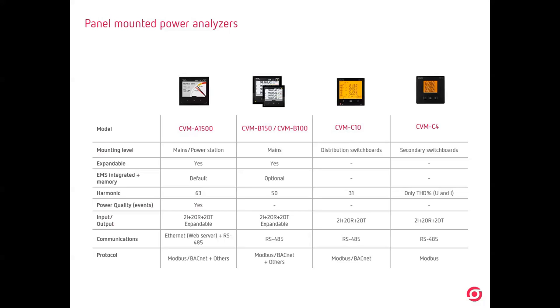Now we are reading harmonics, for checking the quality of consumption. CVM B is expandable. You can expand with more modules, and we are reading up to 50 harmonics. And CVM A is designed to be installed in mains, in the power station, in critical lines, because we have a database. Now we have a web server. We have an EMS software already integrated with memory, 1 year of data. We are reading up to 63 harmonics.